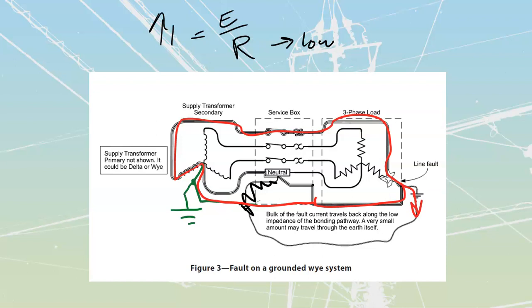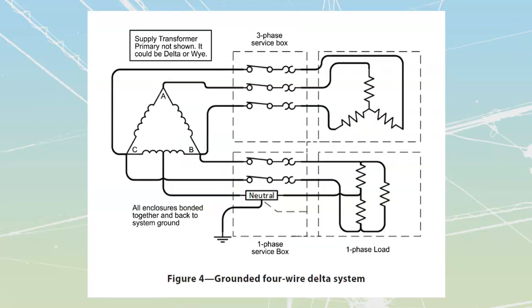The other type of solidly grounded system that we could run into is going to be that high-leg delta, that grounded 4-wire delta type of system. And the grounded 4-wire delta, we know the rules that we have for this one. First of all, we know that our A phase has to be separated out. We cannot keep it inside the same panel. So this is what we're commonly going to see, where we have two service boxes. We'll have a 3-phase box and we'll have a single-phase box. And I say commonly seen as if these things are seen all the time. We don't see these systems very often, but if we do, it is common for them to split these two up.